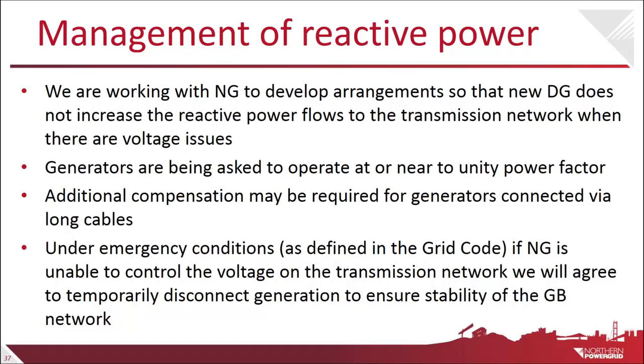National Grid's original approach was that new generation customers would have the capability to operate across the power factor range of 0.95 lead to 0.95 lag, whereas our traditional operating range was 0.95 lag to unity, without the leading power factor. The leading power factor for synchronous generation does cause us significant issues on the distribution network because the stability of the generators can be compromised, as generally the smaller synchronous generators don't have enough inertia to keep themselves stable under fault conditions.